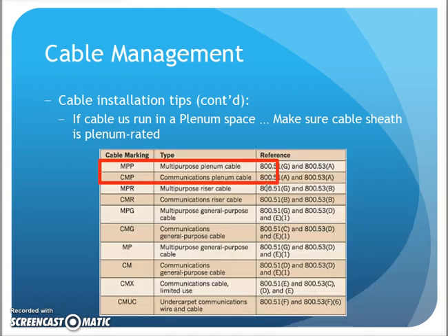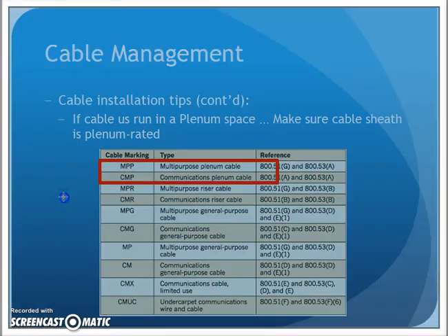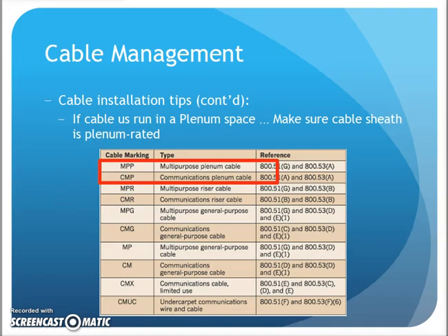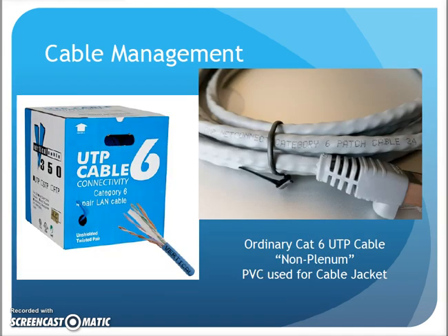On the side of the cable, there's a marking. It actually tells you the type of cable and manufacturer and part number and all that jazz. One of the other codes on there tells you whether the cabling is plenum rated or not. More chances than not, it's going to be like an MPP, CMP kind of thing. The P on the end is key, indicating plenum rated. Even if it's optical fiber, it would be like OFNP, optical fiber non-conductive plenum. So I'd be looking for plenum-rated cabling.